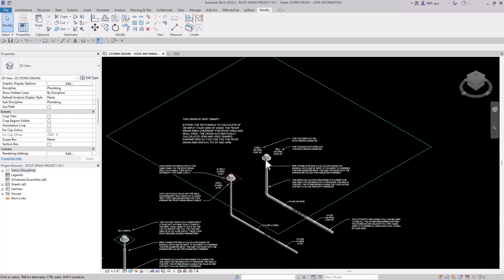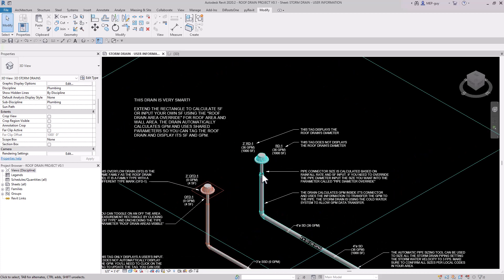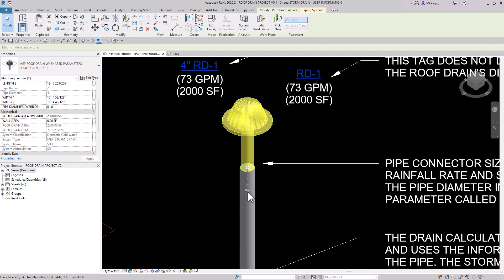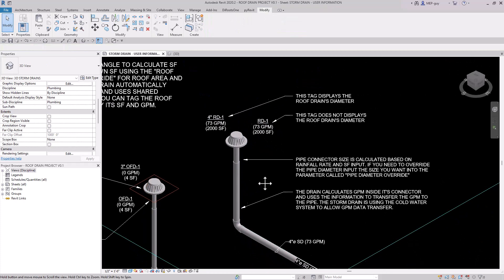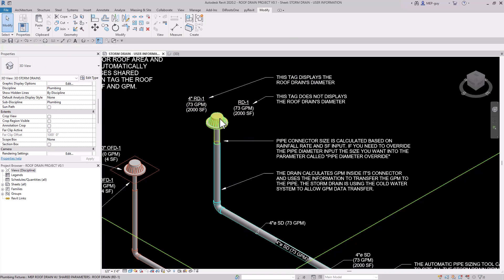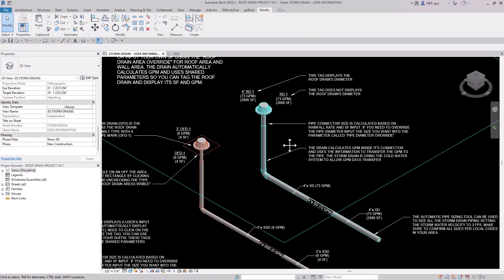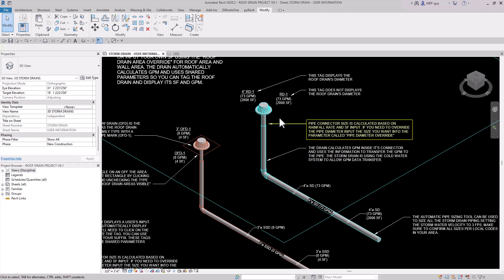Another cool feature is that as I increase the square footage, the roof drain diameter also increases automatically. If I change the square footage to 2,000 square feet, you can see the roof drain updates to a four-inch roof drain, and the connector value also updates to four inches. The GPM actually gets transferred from the roof drain into the piping — clicking on a piece of pipe shows 72.7 or 73 GPM flowing through it. All of this allows us to quickly calculate storm drain pipe sizes.